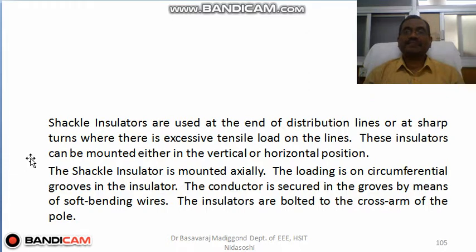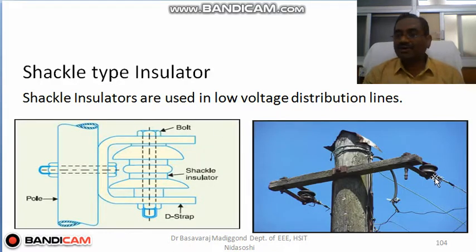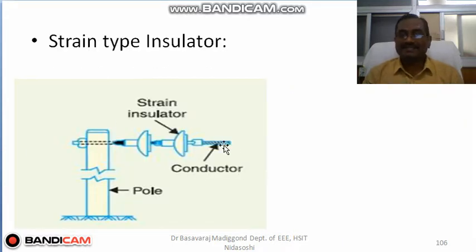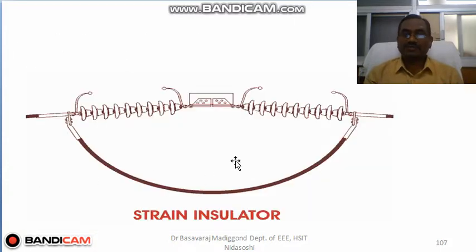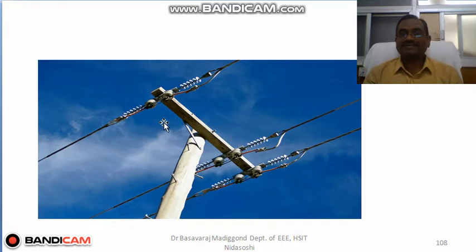These insulators can be mounted either in a vertical plane or a horizontal plane. See here, what is this? Horizontal, and what is this? Vertical. Okay, either it can be positioned in the vertical plane or in the horizontal plane. Okay, see like this. This is a strain insulator, and this is the conductor. This is also used wherever you have a sharp curve or dead end. This is one more type of insulator, strain type insulators. See, this is one more example of strain type insulators. Like this, you can see here.